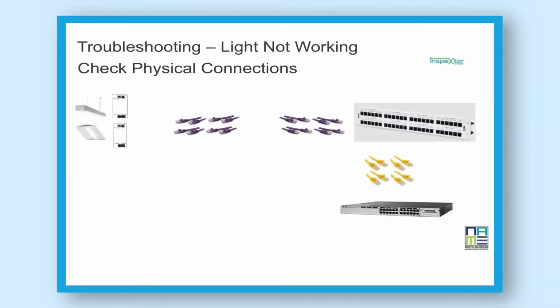Again, light is not working. First thing I'm doing, I'm verifying the physical connection. And I'm verifying the physical connection from the fixture all the way down to the switch. This simply means that you can come from either side of the spectrum. You can go from the fixture down to the switch, or from the switch down to the fixture. You ran the cable, you patched it.